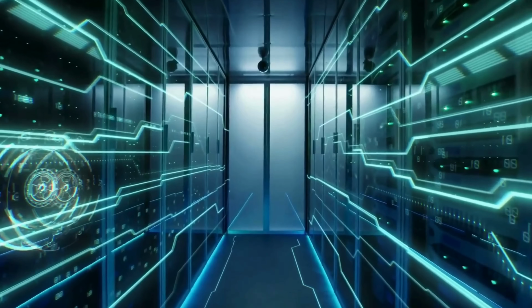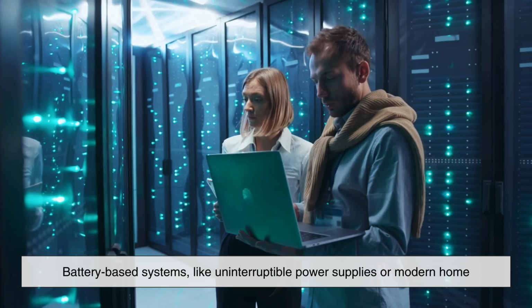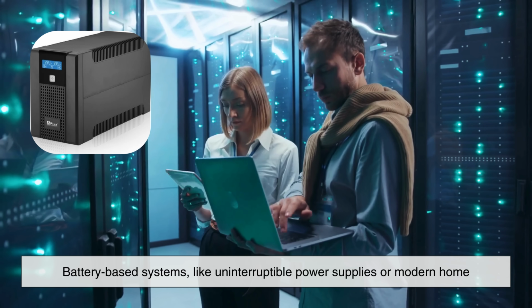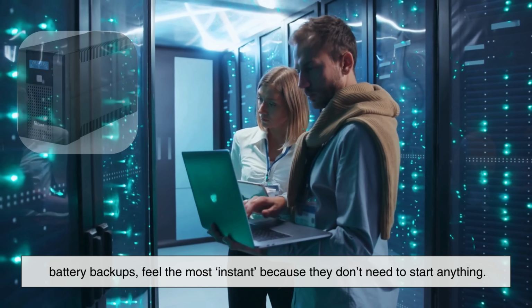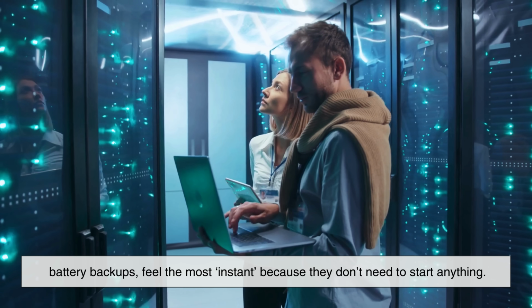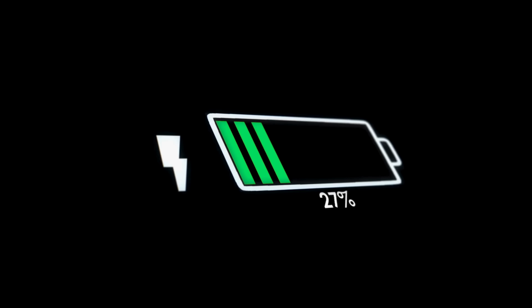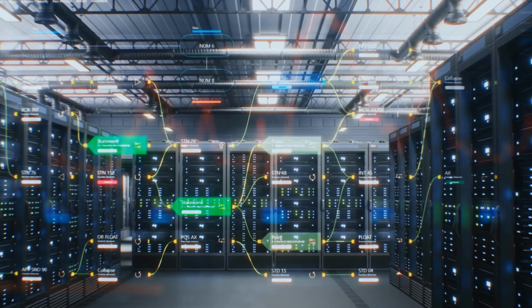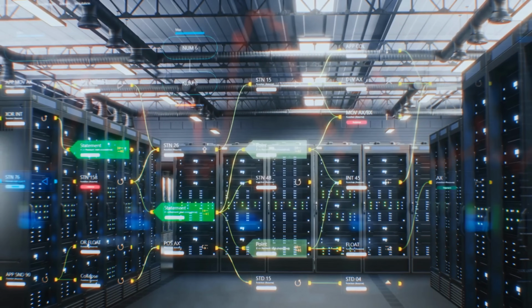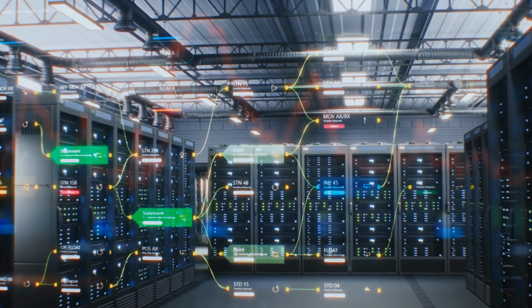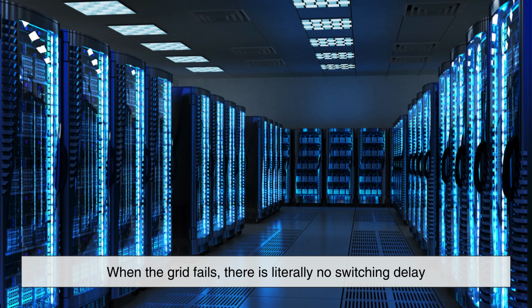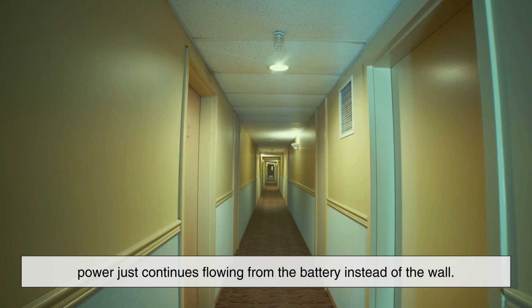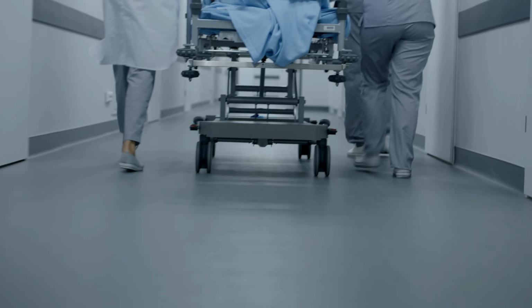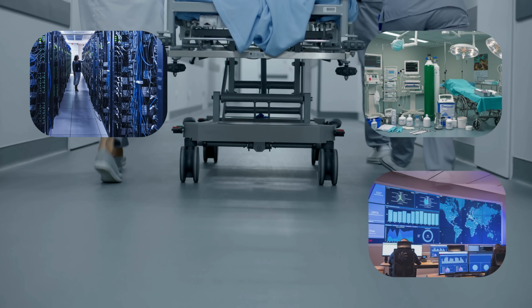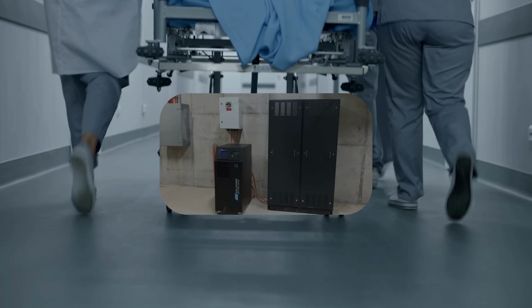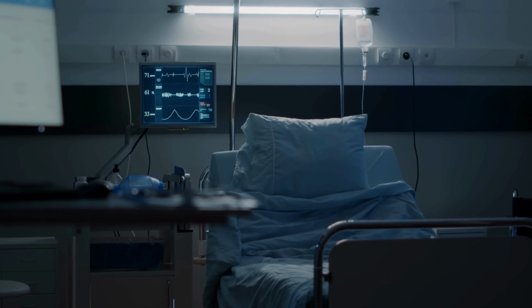Not all backup power systems are equal when it comes to speed. Battery-based systems like uninterruptible power supplies, or modern home battery backups, feel the most instant because they don't need to start anything — the batteries are already energized and standing by. In many UPS systems, your devices are actually being powered by the battery at all times, while the grid simply keeps the battery charged. When the grid fails, there is literally no switching delay; power just continues flowing from the battery instead of the wall. That's why servers, hospital equipment, and critical communication systems rely heavily on UPS units. To them, a blackout is just another normal moment.